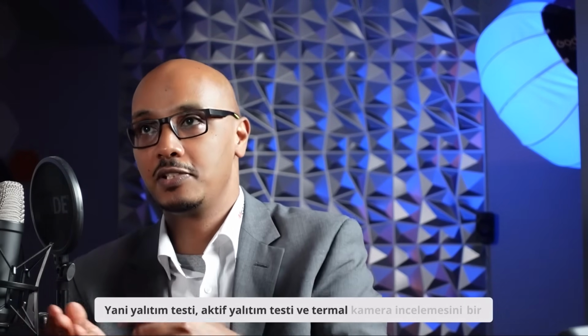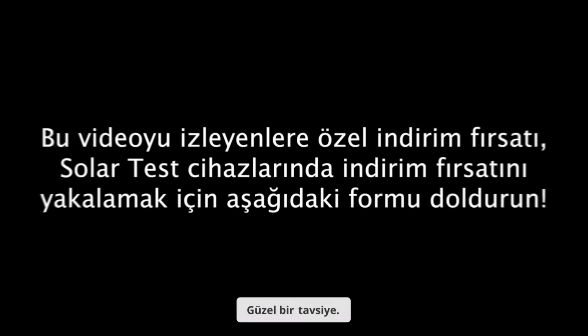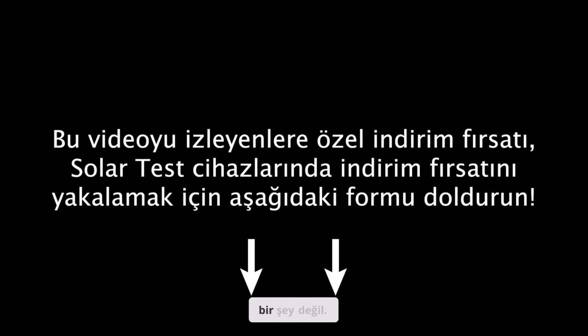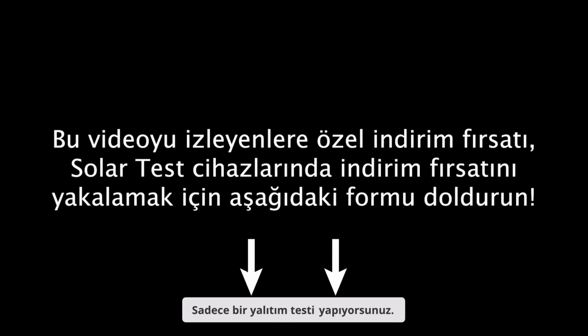So you can combine an active insulation test with a thermal camera survey at the same time and discover problems that way. It's a nice tip, not the standard approach of just doing an insulation test, finishing it, and then doing a thermal scan separately. But sometimes combining these things helps.